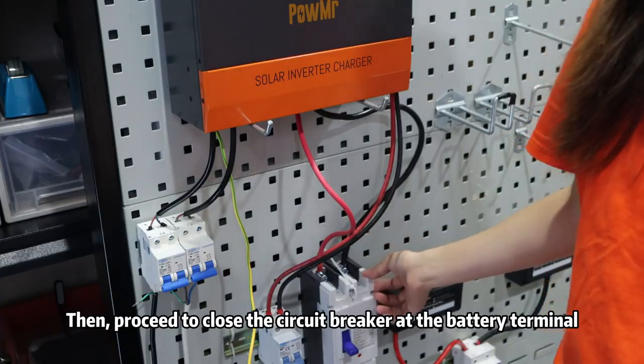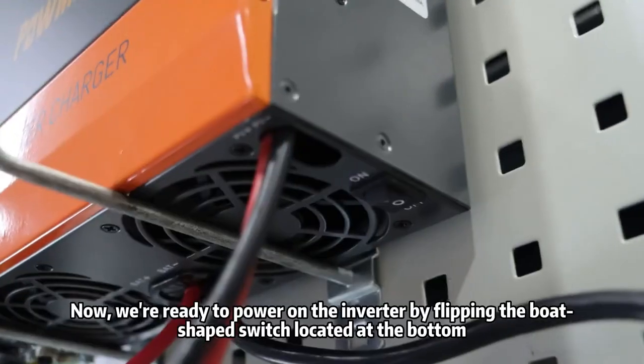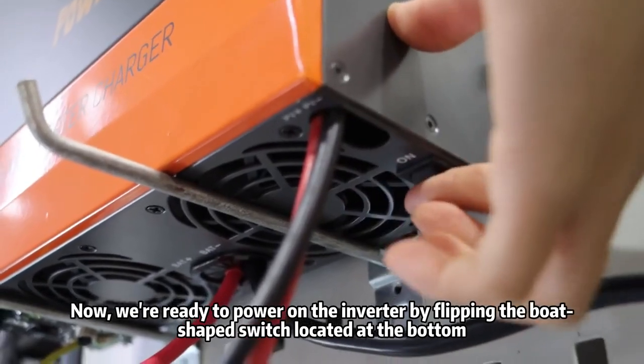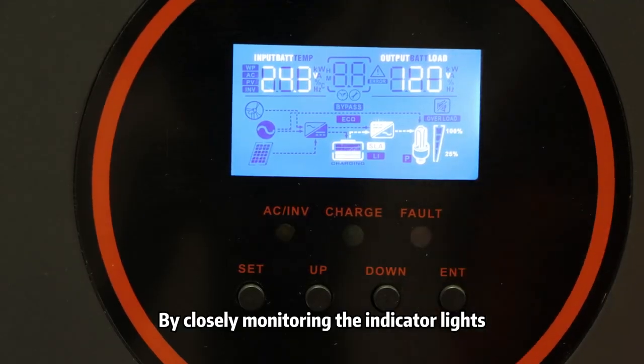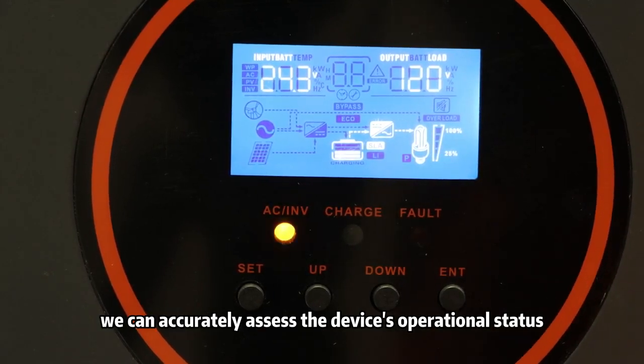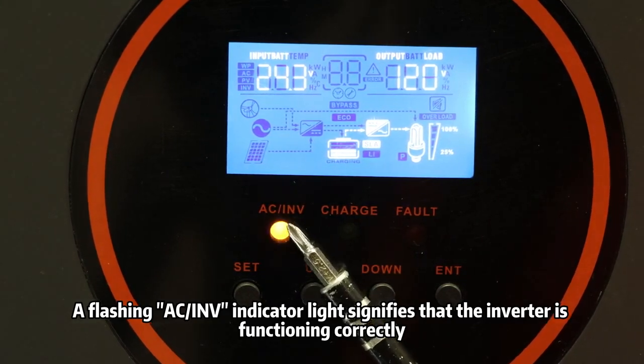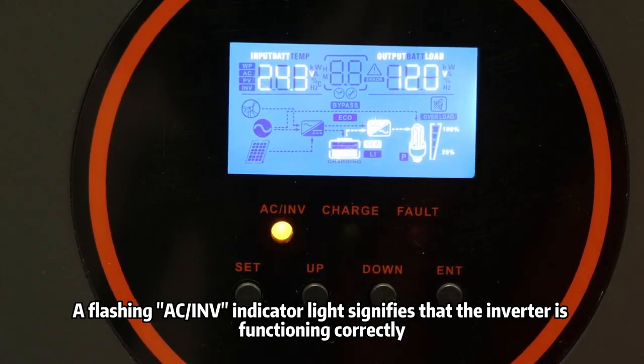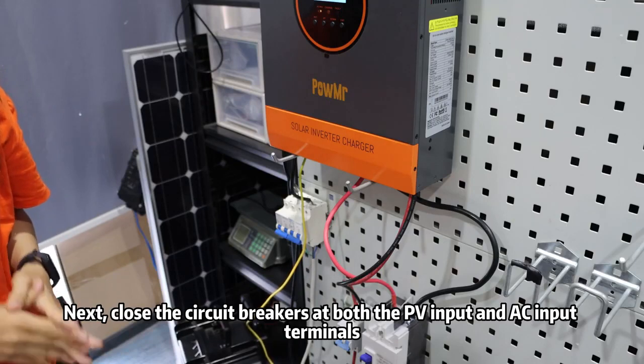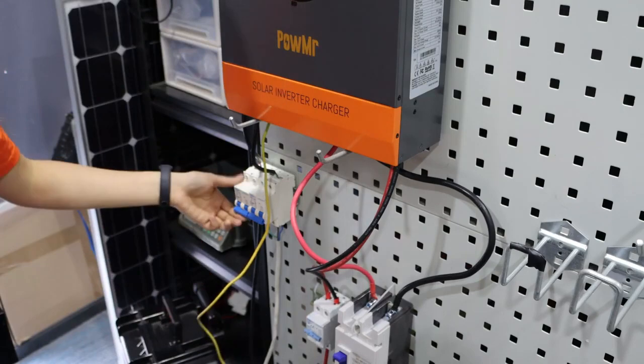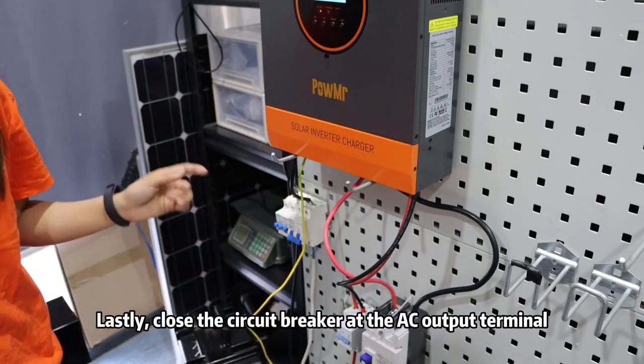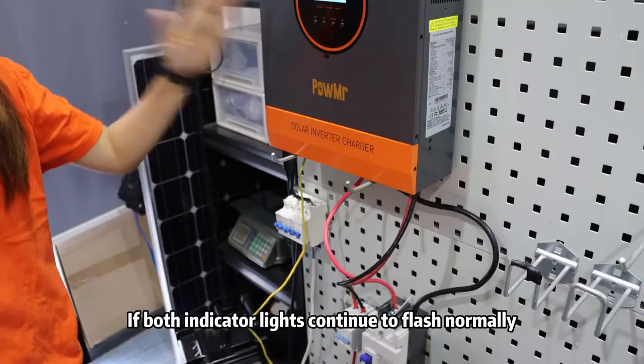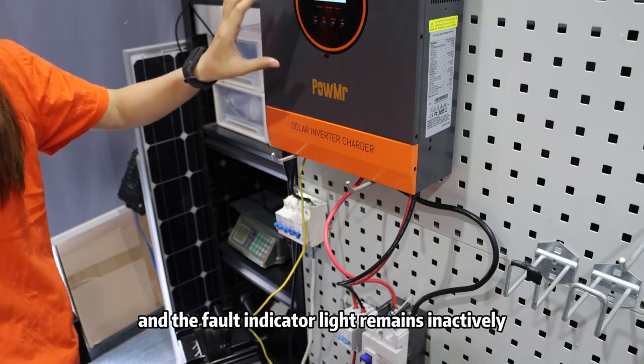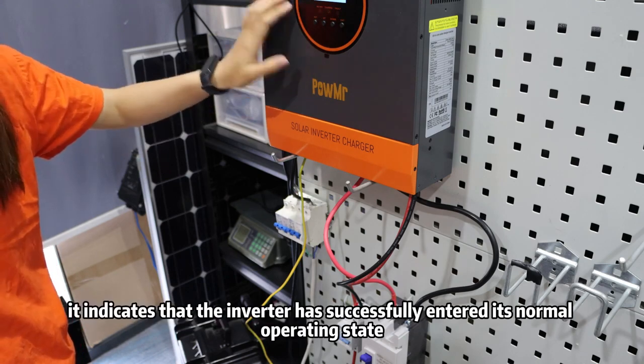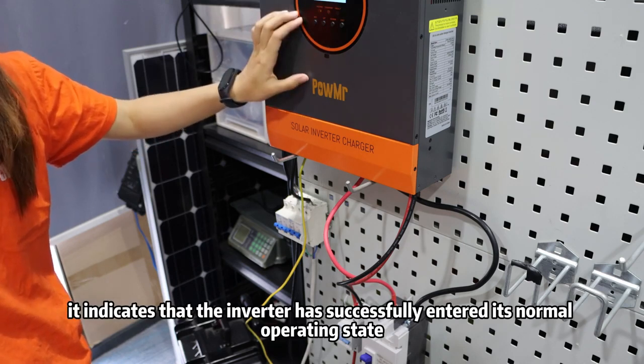Then proceed to close the circuit breaker at the battery terminal. Now we are ready to power on the inverter by flipping the switch located at the bottom. By closely monitoring the indicator lights, we can accurately assess the device operation status. A flashing AC INV indicator light signifies that the inverter is functioning properly. Next, close the circuit breakers at both the PV input and AC input terminals. Lastly, close the circuit breaker at the AC output terminals. If both indicator lights continue flashing normally and the fault indicator light remains inactive, it indicates that the inverter has successfully entered its normal operating status.